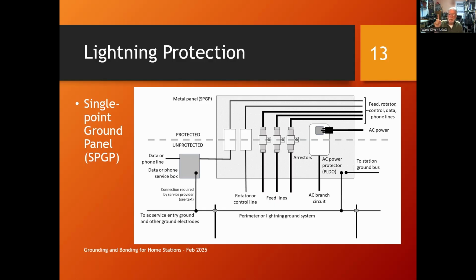So you run a branch circuit from your circuit breaker box over to this AC power protector that's on the single point ground panel. And then you run another cable that goes into your station and supplies your equipment. Most stations can run from a single branch circuit. I think most of us have thought about this, and maybe we have one breaker in our service panel that says radio or something like that. You can pretty much run a bunch of computers and a bunch of 100-watt radios off of one circuit. If you've got amplifiers, you would run a separate circuit for them.